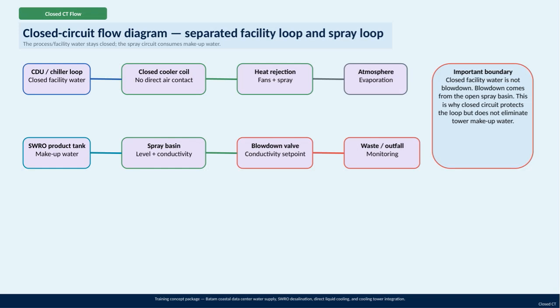Here we have the closed circulating water flow system, which is designed to keep the facility loop completely closed, meaning the water inside the process or facility doesn't leave this loop. This is important because it minimizes water loss and contamination inside the cooling loops. At the same time, there's a separate spray loop that's open to the atmosphere. This spray circuit is where water evaporates, and as a result, this loop consumes makeup water to replace what's lost through evaporation. The integration of components like the SWRO desalination system and direct liquid cooling in this setup ensures efficient water supply and cooling for Batam Coastal Data Center.